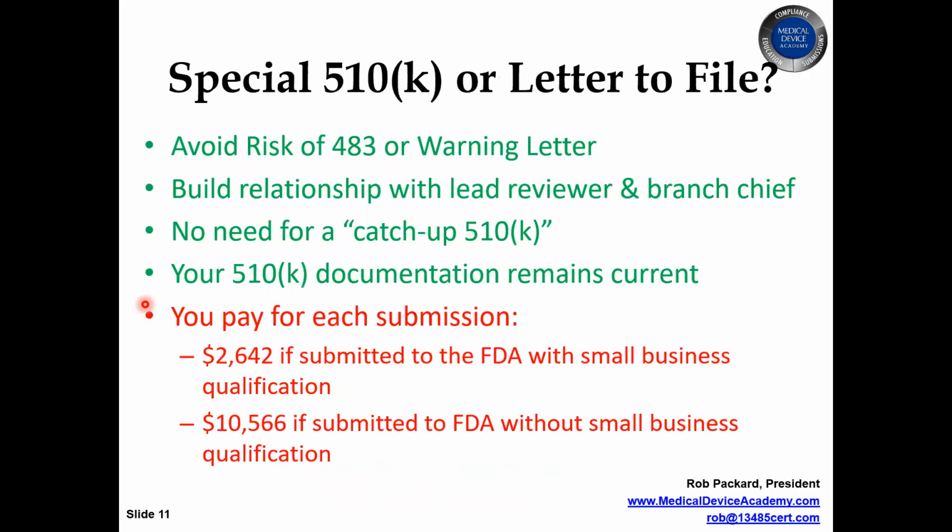Special 510K or letter to file. So a lot of times people are trying to decide, should this submission be a special 510K or should it be a letter to file? And so the top 3 reasons are the benefits for why you would do a 510K. And the bottom red reasons are the reasons why people most of the time don't want to do a 510K, even a special 510K, and why they would prefer to do a letter to file.